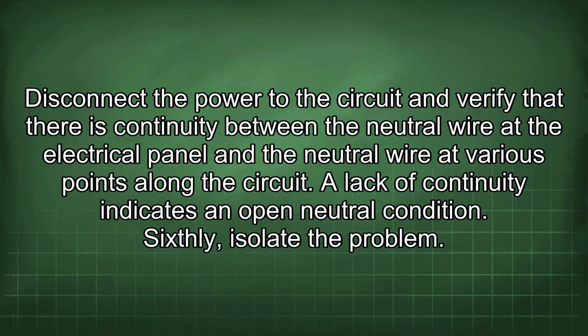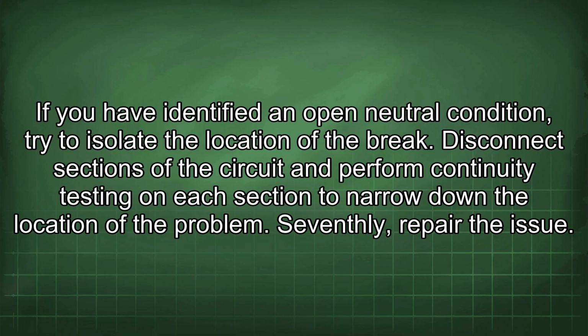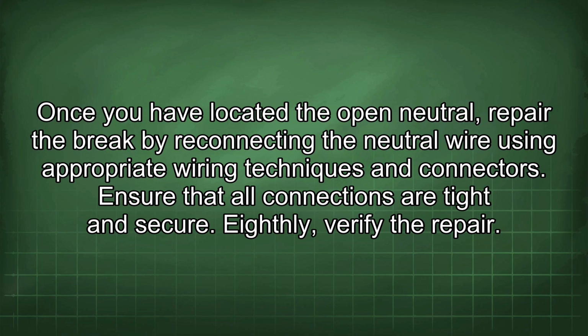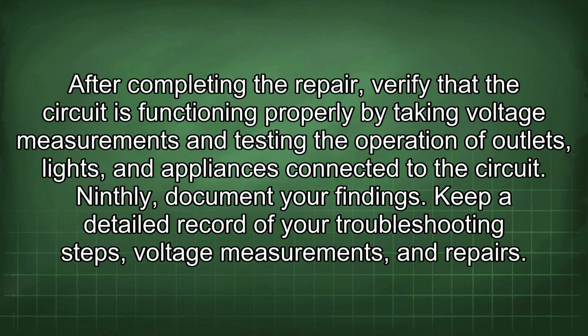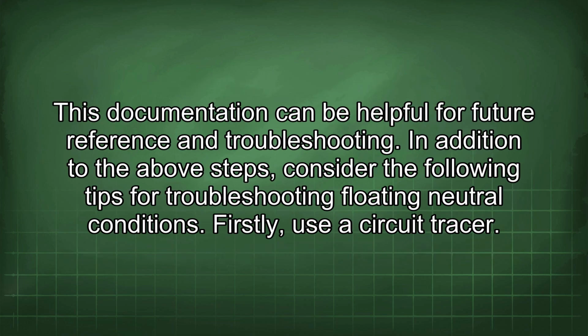Sixthly, isolate the problem. If you have identified an open neutral condition, try to isolate the location of the break. Disconnect sections of the circuit and perform continuity testing on each section to narrow down the location of the problem. Seventhly, repair the issue. Once you have located the open neutral, repair the break by reconnecting the neutral wire using appropriate wiring techniques and connectors. Ensure that all connections are tight and secure. Eighthly, verify the repair. After completing the repair, verify that the circuit is functioning properly by taking voltage measurements and testing the operation of outlets, lights, and appliances connected to the circuit. Ninthly, document your findings. Keep a detailed record of your troubleshooting steps, voltage measurements, and repairs. This documentation can be helpful for future reference and troubleshooting.